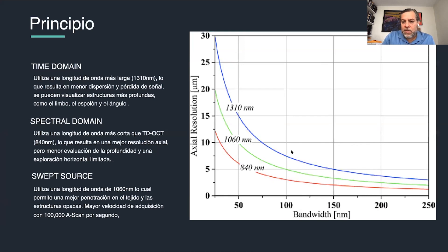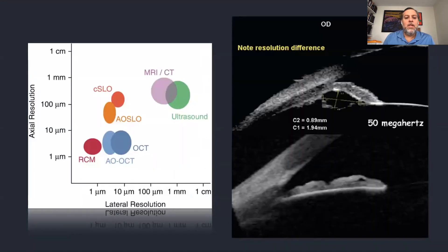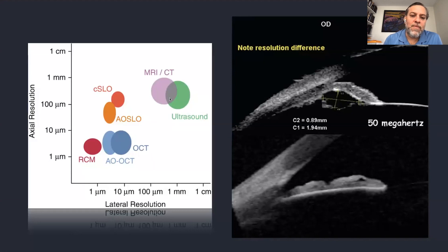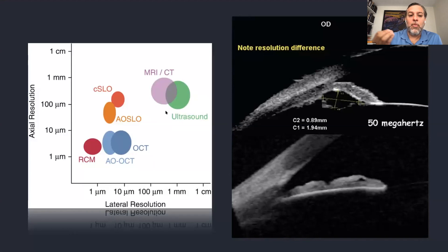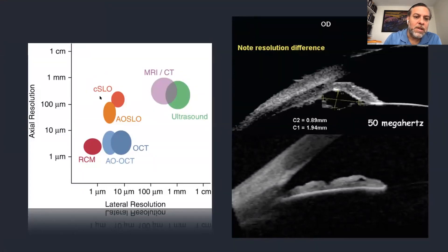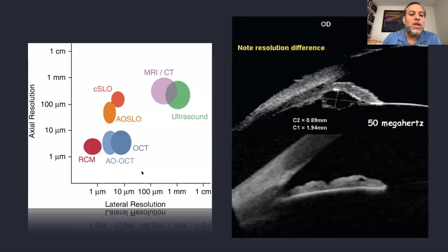Regarding resolution: at 1310 nanometers you get better axial resolution; at 1050 nanometers you get standard resolution; at 840 nanometers the resolution is lower for the anterior segment. Comparing OCT with other imaging technologies, ultrasound used for anterior segment has resolution around 1 millimeter — almost the same as CT scan or MRI. For imaging smaller tissues, we need scanning laser ophthalmoscopes or OCT, which achieve around 100 microns.